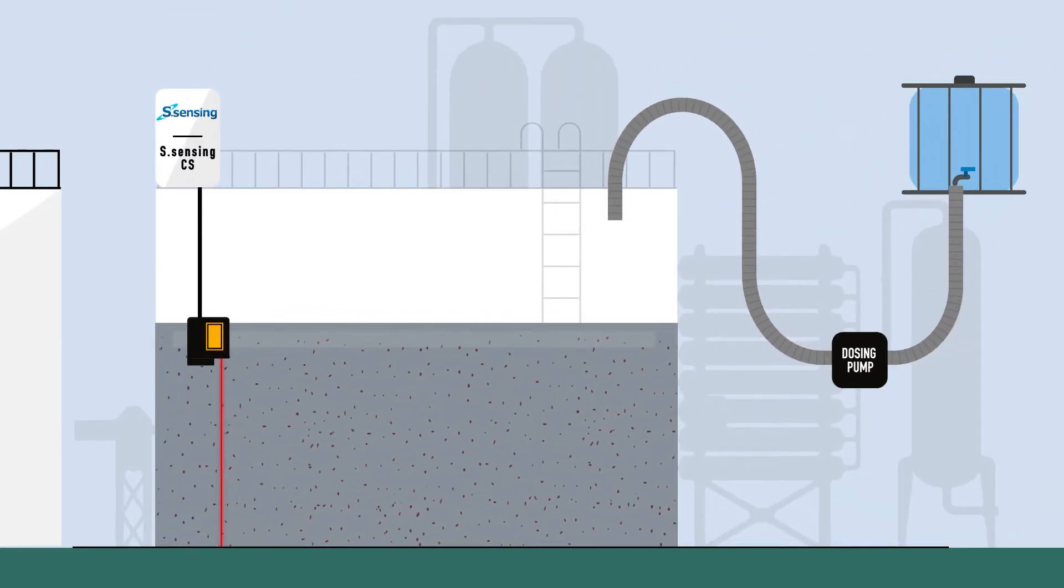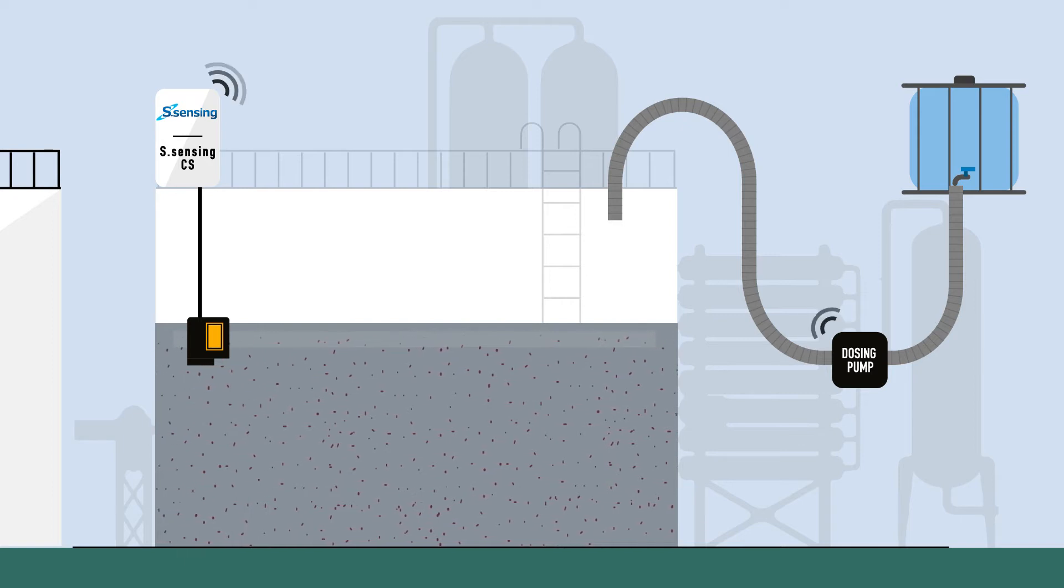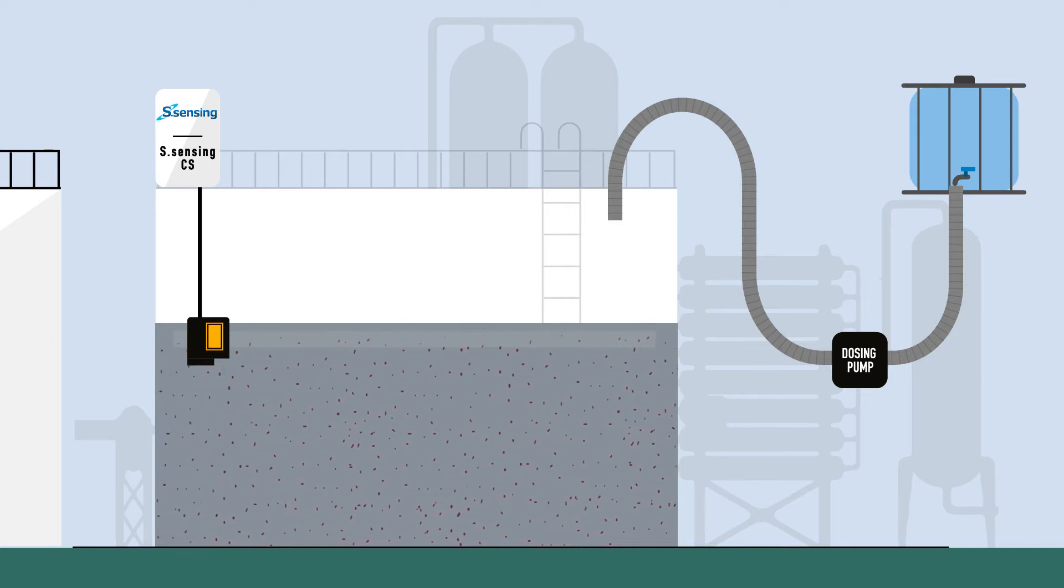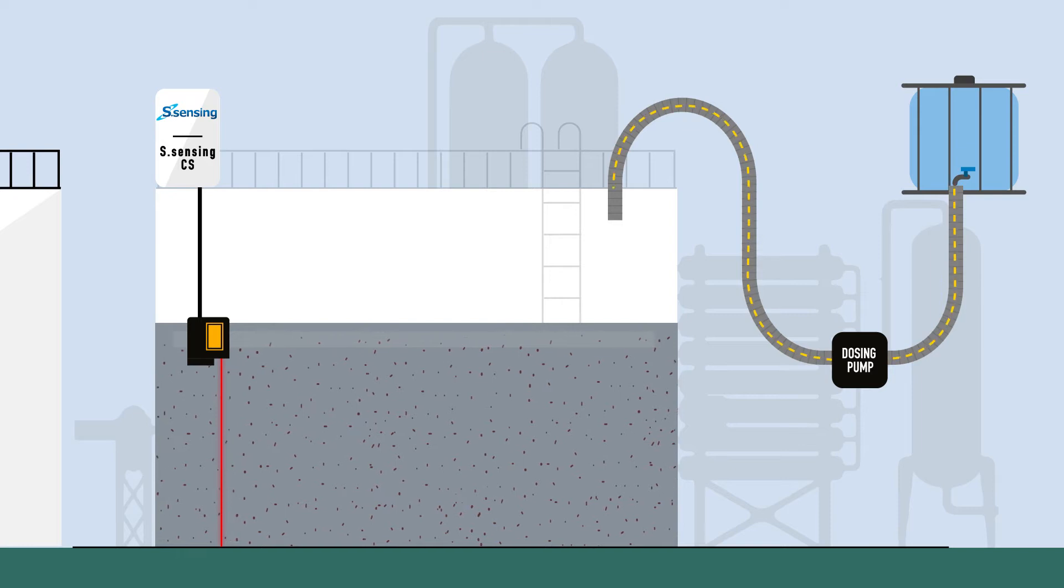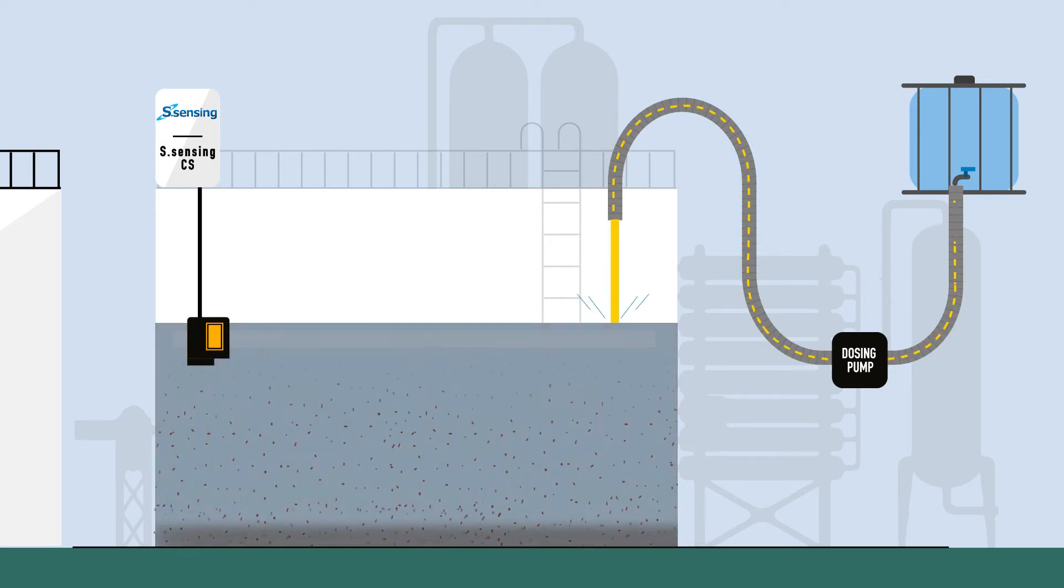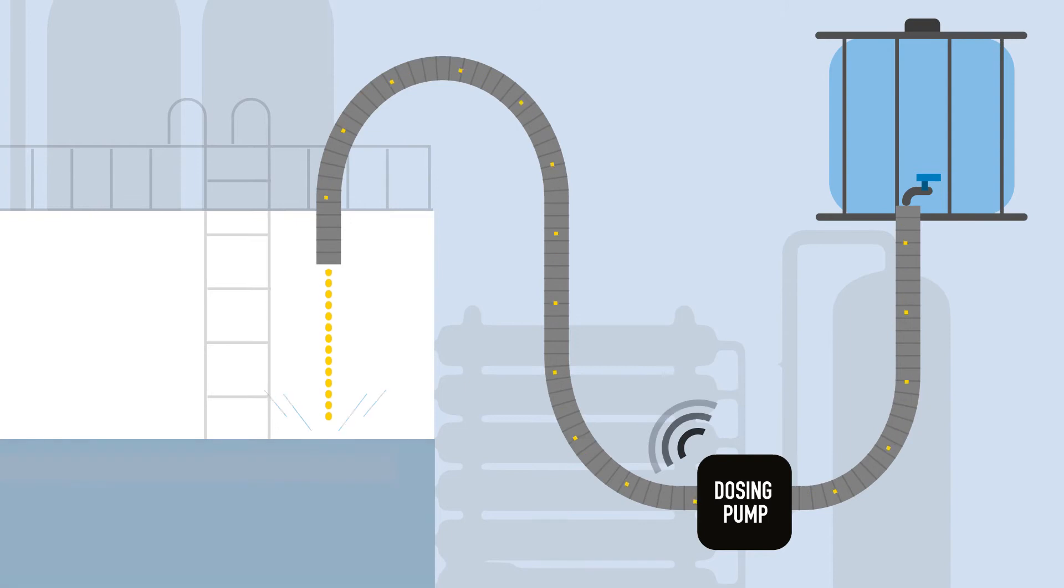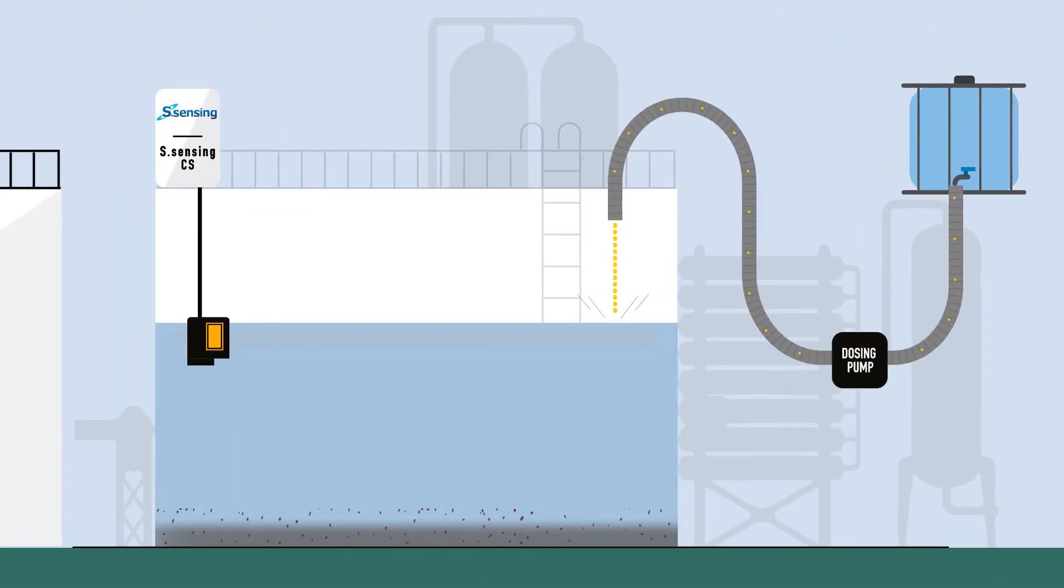The advantage of a continuous measuring of turbidity is that it enables the S-Sensing CS wastewater monitoring system to control the product dosage already with the data from the flocculation tank which means before the actual sedimentation process.